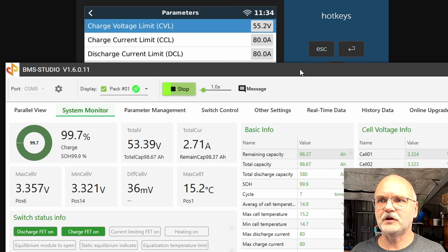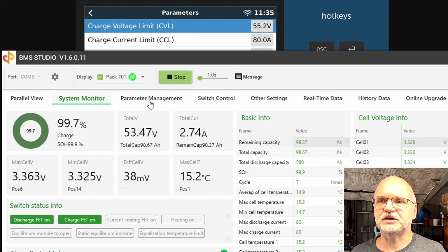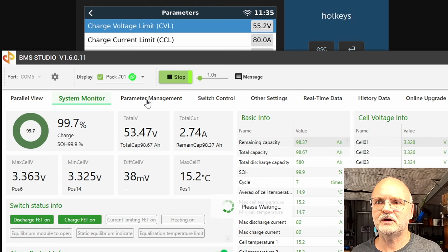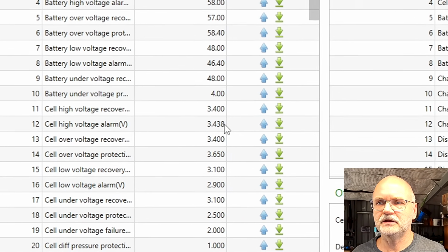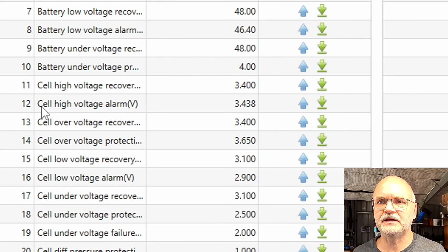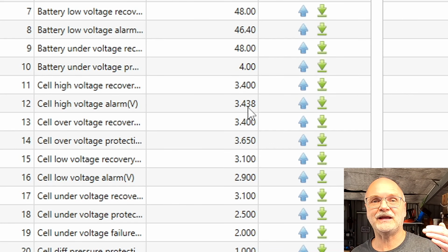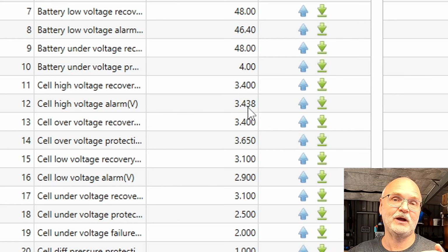Okay, I have now turned off the load again, so I'm going to recharge the battery. And while we are charging, we want to have a quick look at the parameter management. So here we can see the number 12, the cell high voltage alarm. And this value here times 16 is your threshold you need to exceed with your battery voltage, and then wait for 30 minutes to reset to 100%.